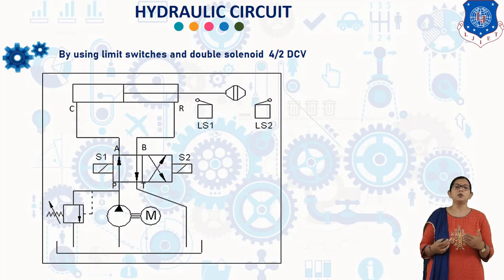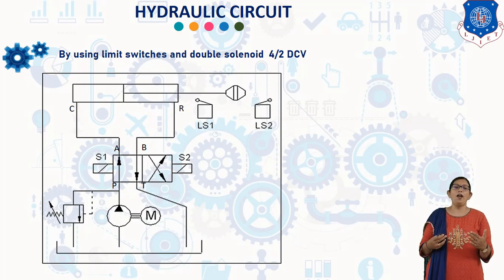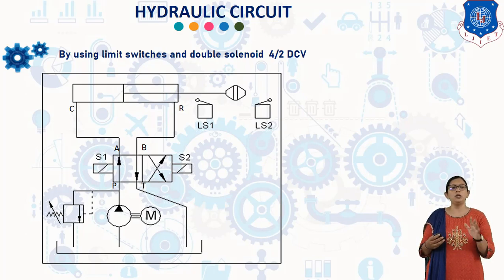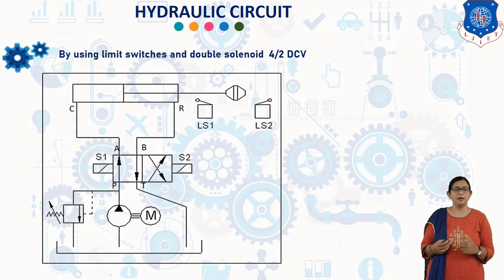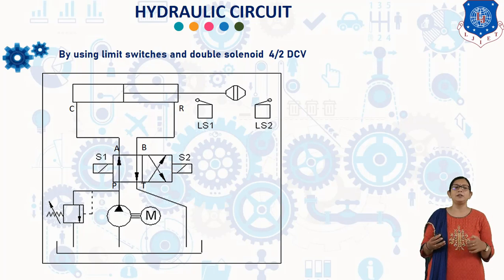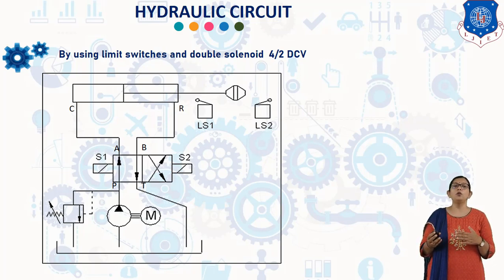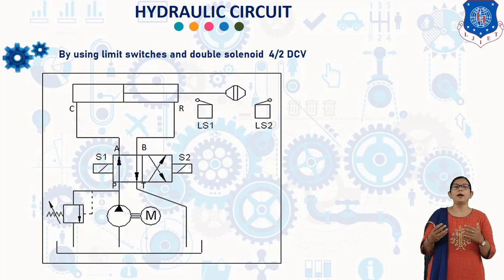Thus, automatic reciprocation is achieved. In the first position of the 4/2 directional control valve, oil under pressure flows from P to A and B to T. As the cylinder extends, by the end of the extension, the cam attached to the piston rod presses the limit switch Ls2. Hence, electric current flows to solenoid S2, and the spool of the 4/2 DCV shifts to the second position.